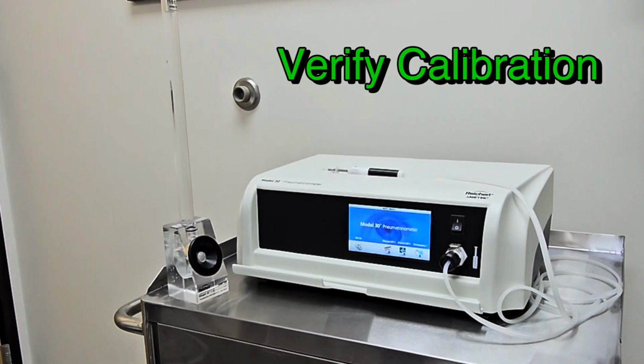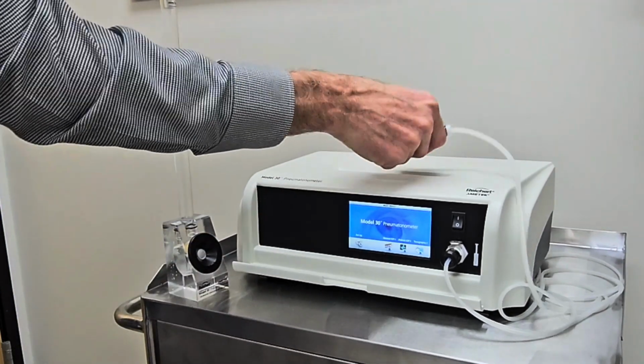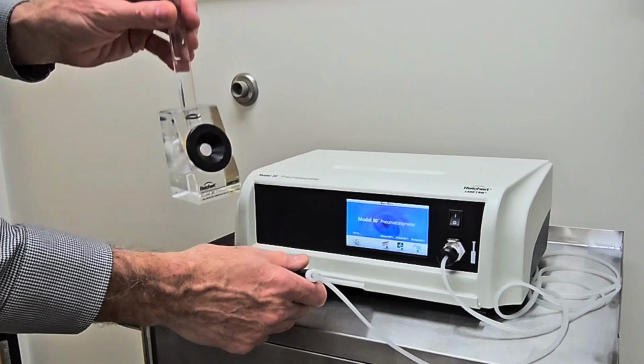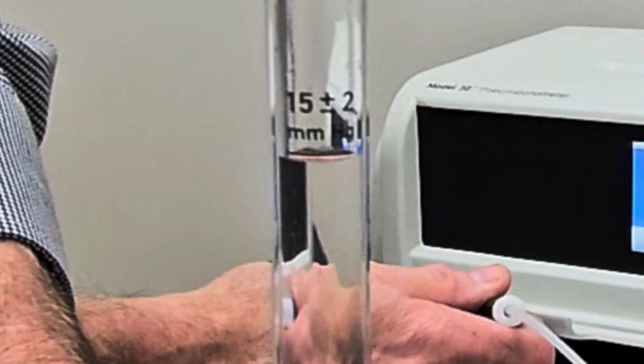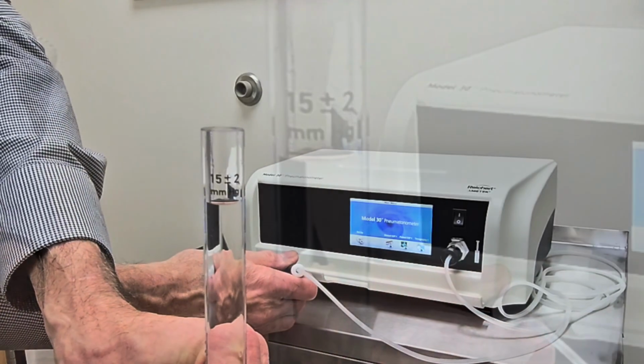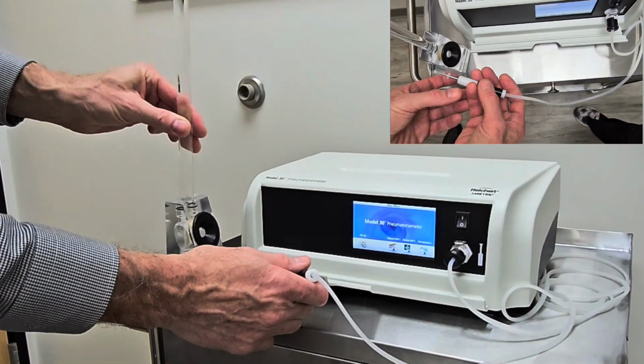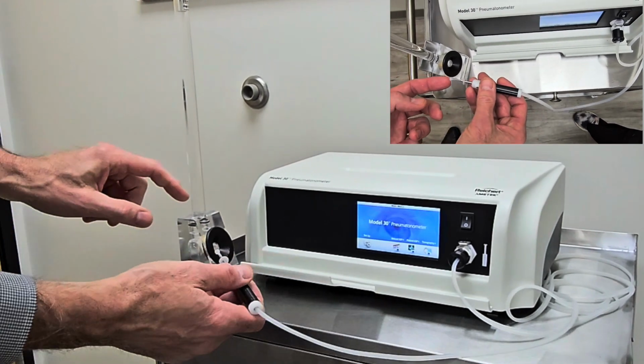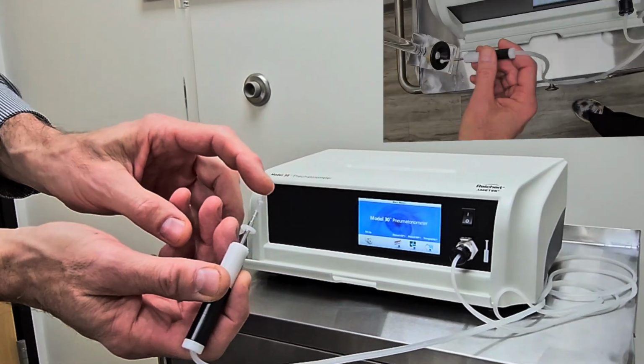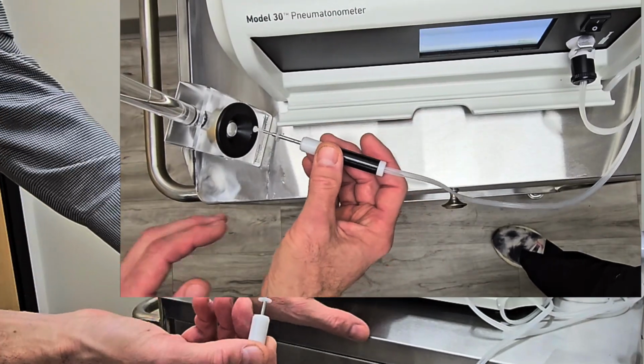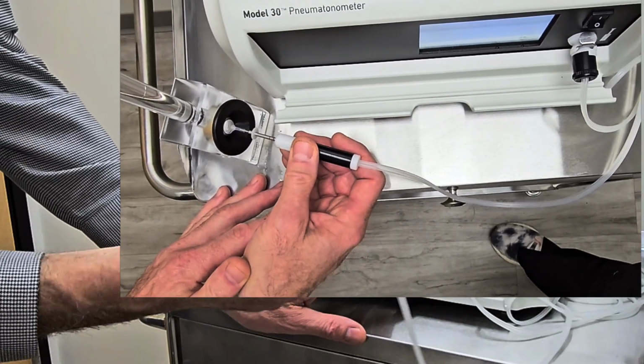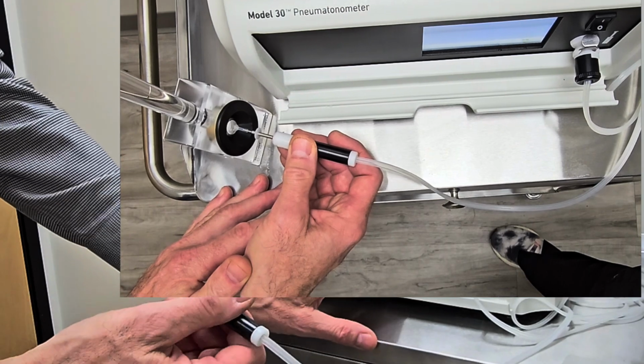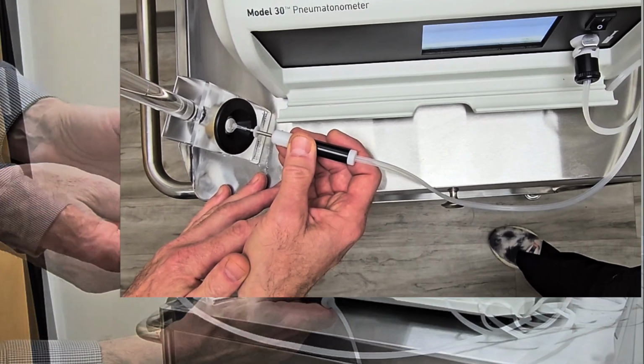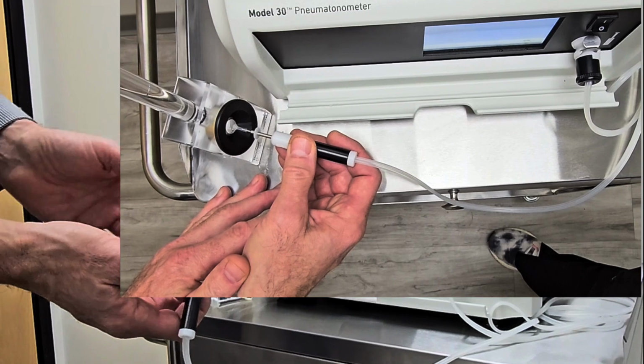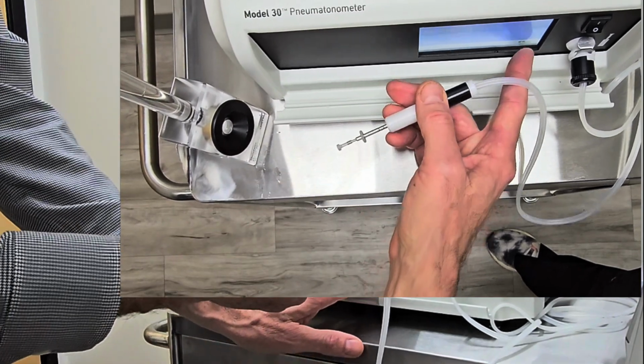So the first thing we do is we verify the calibration. Notice this is not calibrating, this is verifying calibration. So you fill this with water to the hash mark, and then we're going to start the machine up. You have to put a little bit of water on the tip. It has to run with liquid. It can't run dry. And then we do a standard tonometry. You'll listen for the tone. You'll put it in between the two hash marks. We'll talk about this in the next video. And when the tone changes, you're all done.